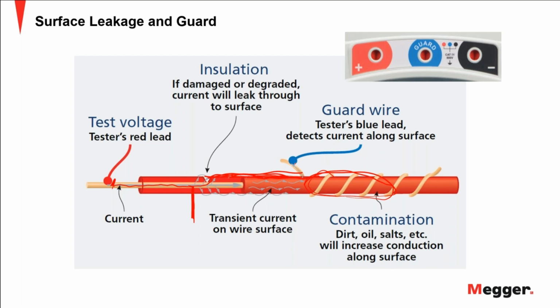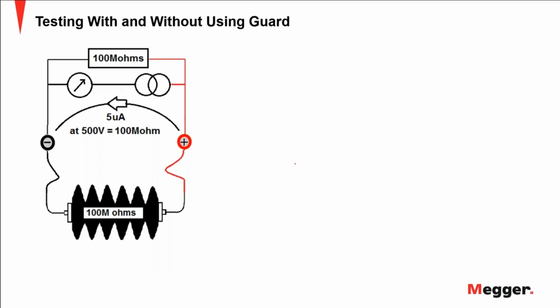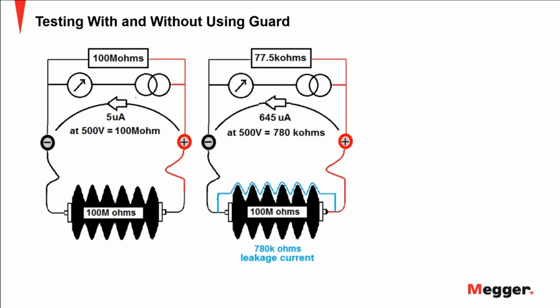So the guard conductor helps you to run the test, and this is a quick example before ending the presentation. Let's say that I have this resistance that is 100 megaohms, and I apply the insulation resistance test, and I get that result. If I spray water on all of these surfaces, now I have an additional path for current to flow through the surface.